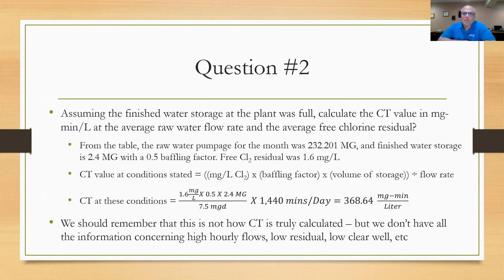You can see how I laid this out here. I went into the table and I saw that the raw water pump is for the month 232.201 million gallons. The finished water storage was 2.4 million gallons and has a baffling factor of 0.5. The free chlorine residual, and that's what I use for CT, not total but free, was 1.6 milligrams per liter. So the CT value at these conditions would be the milligrams per liter chlorine times the baffling factor, times the volume of storage divided by the flow rate. For those not too familiar with CT value, basically what the regulators are doing is having you calculate a detention time, which is always the volume divided by the flow.